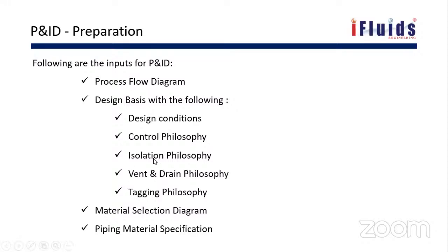And then isolation philosophy, in the sense, if you have a pump, you need to isolate it during maintenance. So during that maintenance, you'll be isolating. So whether I need to put one isolation valve or two isolation valves, those things will be captured in the isolation philosophy, and then the vent and drain philosophy.